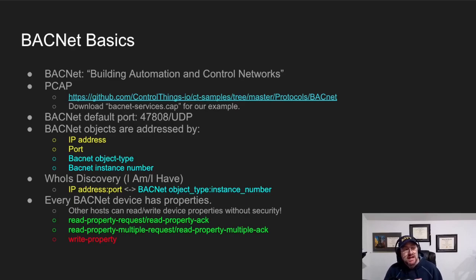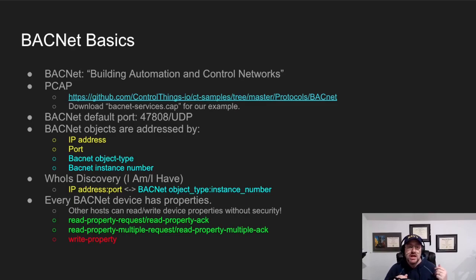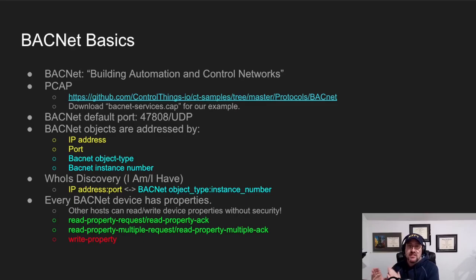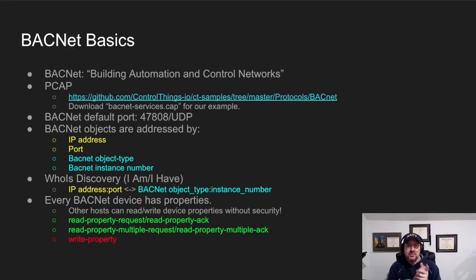In BACnet, there's a WhoIs discovery protocol that happens, kind of like ARP. There are WhoIs, IAm, and IHave messages, and the purpose of this protocol is to map the IP address and port to the BACnet object type and instance number pair. I'm going to show you examples of that in some Zeek logs coming up.